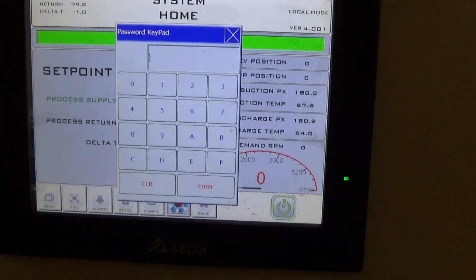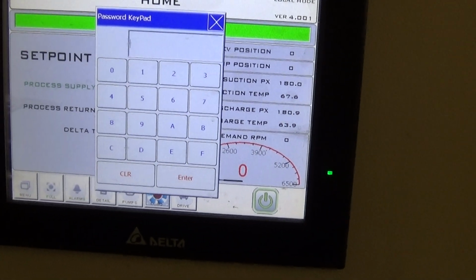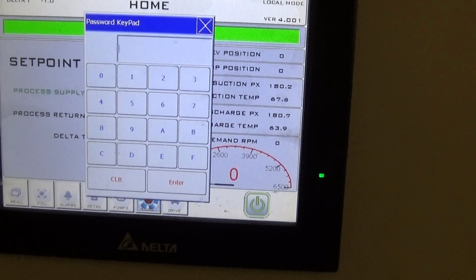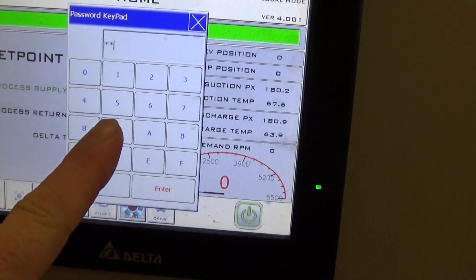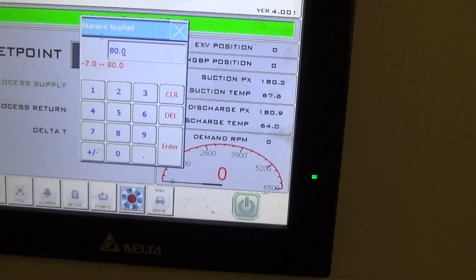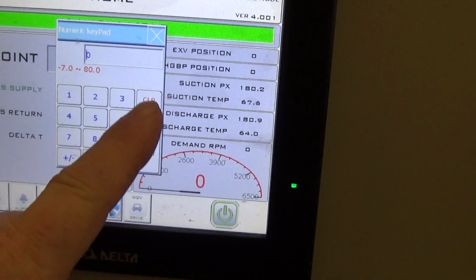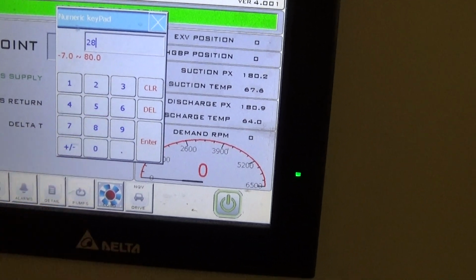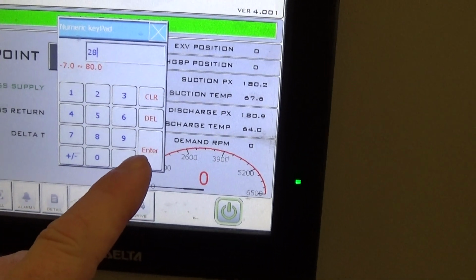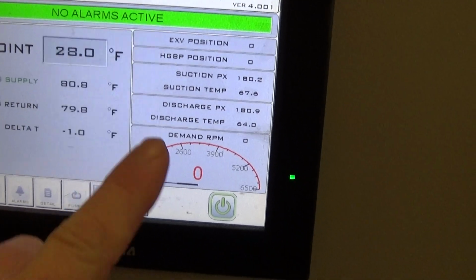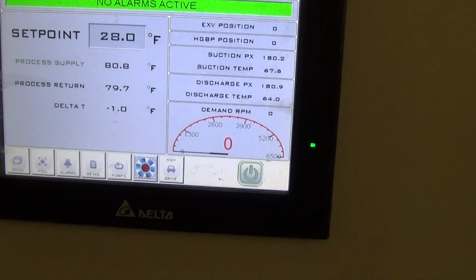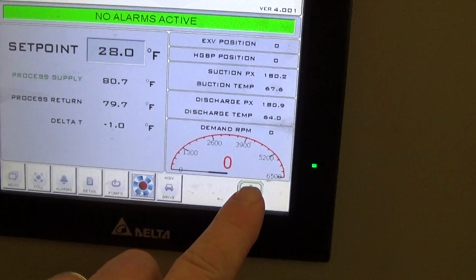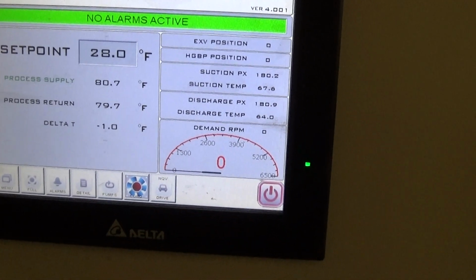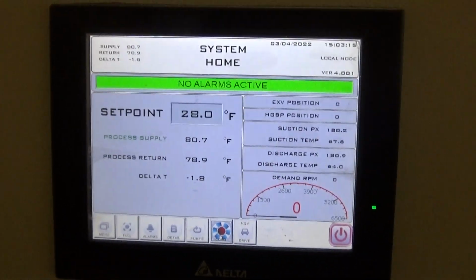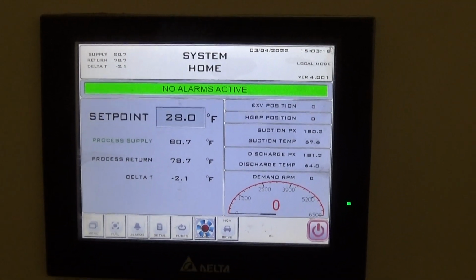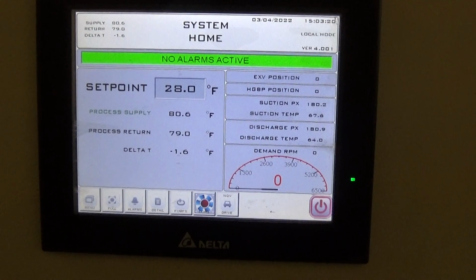Password for user accessible parameters is 9999, 4 nines. Okay, and we're going to change the set point down to 28 degrees Fahrenheit. We're running 40% glycol in the shop, by the way. Enter. Okay, then we're going to go to the green button here. Start the chiller. And that starts our pump.